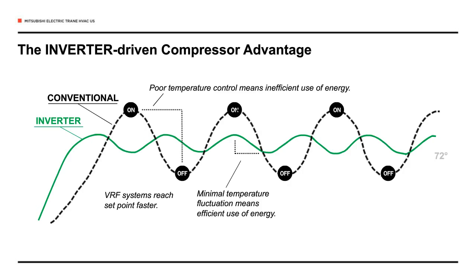Heating and cooling loads continue to get lower as passive house and other methodologies improve building envelopes and increase overall efficiency. Conventional systems use a fixed speed compressor which cycles a unit on and off whenever the room dips below desired temperatures. That's depicted here by the black dotted line. This type of system relies on an all or nothing approach, with the compressor running at either 0 or 100%. This can lead to unpleasant temperature swings as the system strains to maintain a constant temperature. Inverter compressors, on the other hand, are always running in the background, adjusting the compressor and modulating the speed in real time. That's represented by the green line.